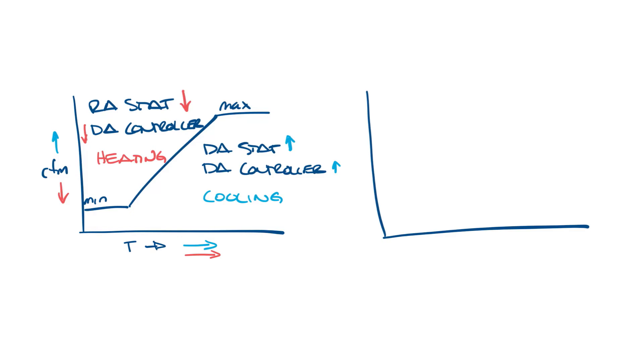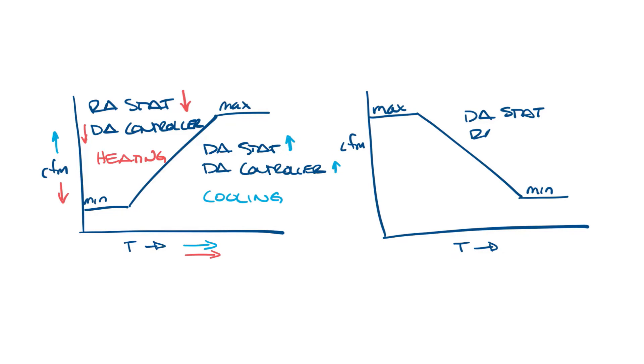If you have a direct acting thermostat with a reverse acting controller, the direct acting thermostat sees a room temperature increase and increases the thermostat signal to the reverse acting controller. The reverse acting controller would reduce the CFM in response to an increase in thermostat signal, so you'd be sending less air to the space — and you'd want to do this during heating.